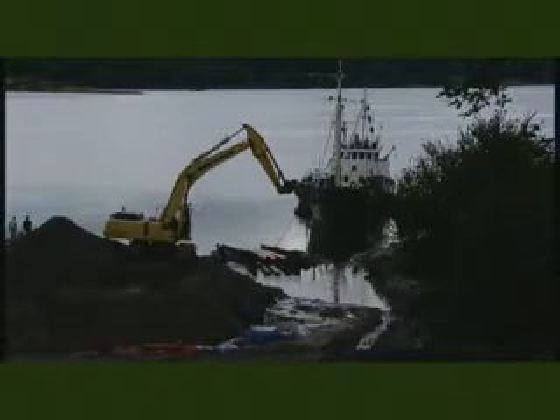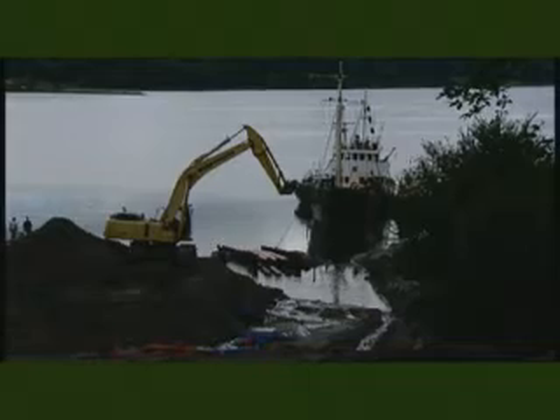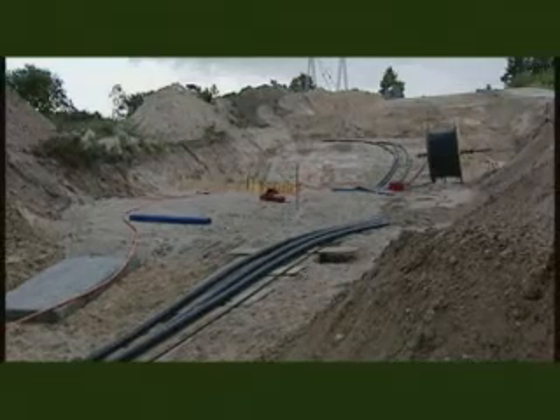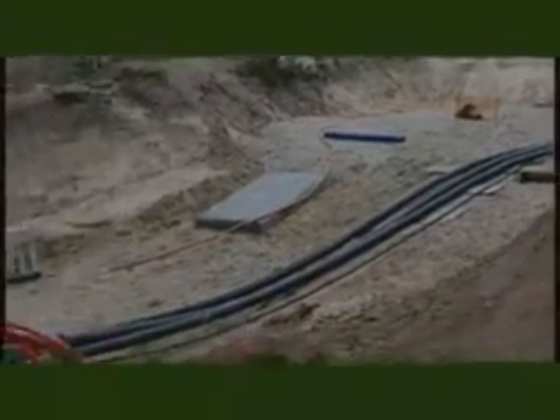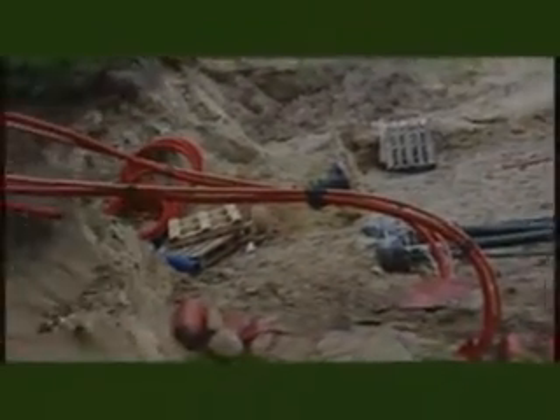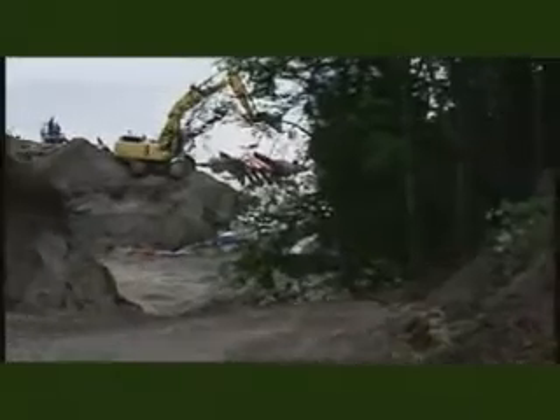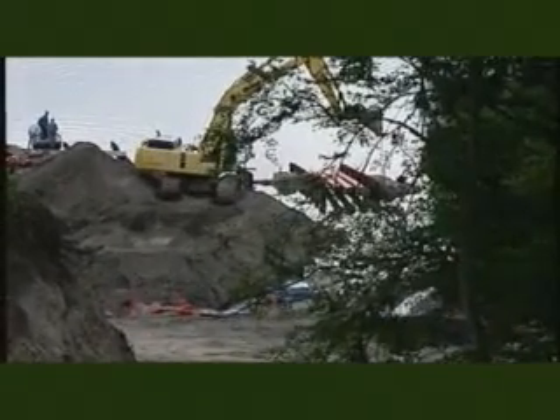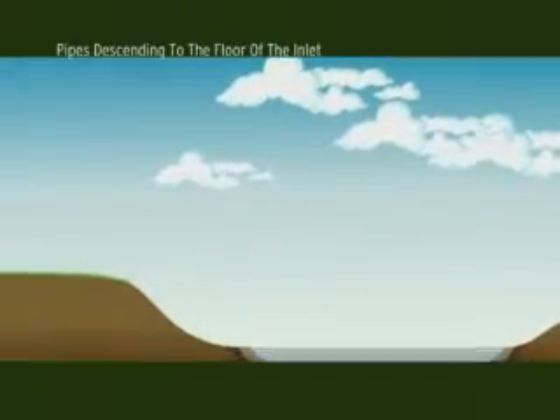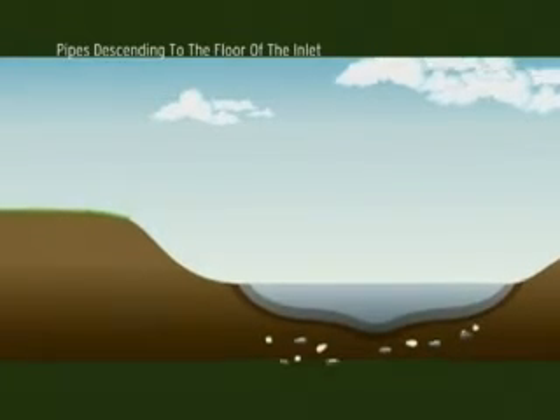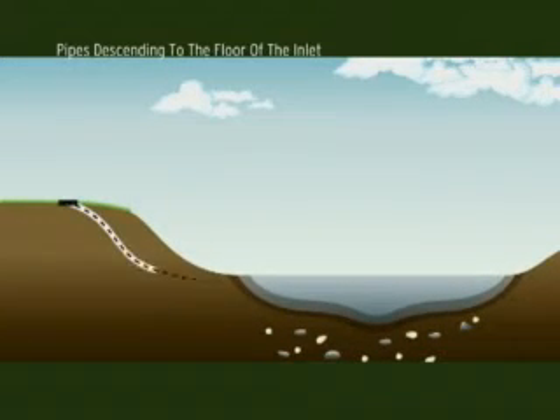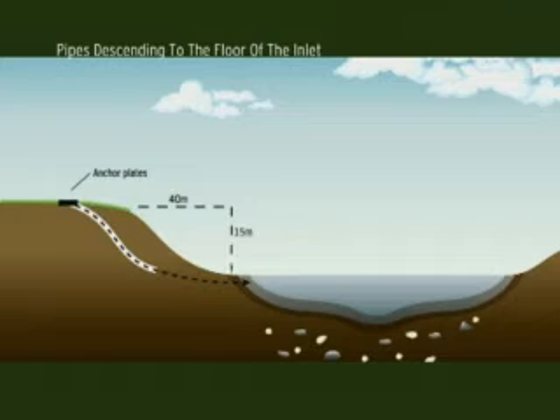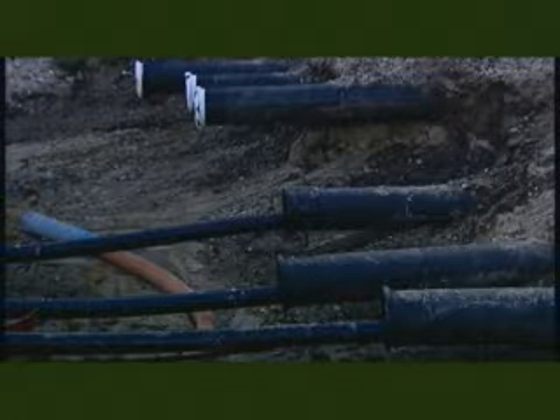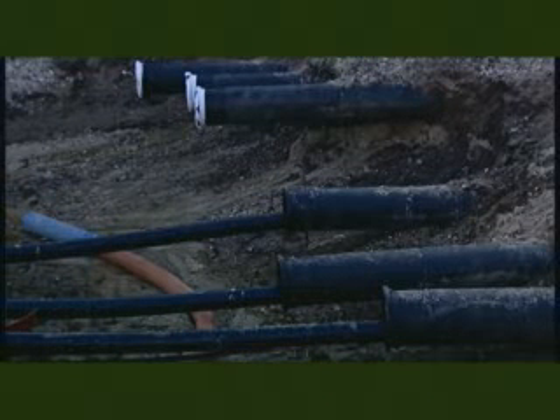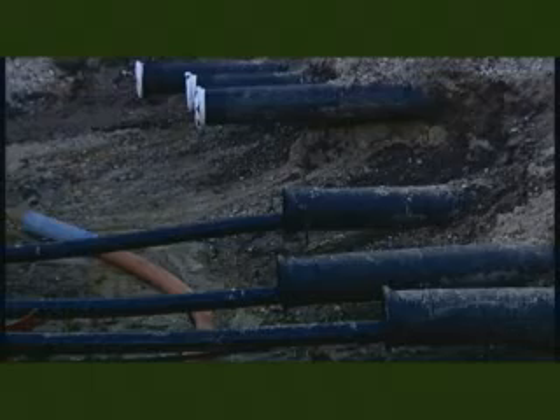To ensure that the cable does not slide down onto the beach of its own accord after laying, an anchor plate was established at the top of the slope, to which the cable could be secured. The bank down to the beach is so steep that it's not possible to lay the cables in open trenches on site. It was therefore necessary to carry out a controlled directional drilling beneath the slope. The cables are fed through the pipes down to the beach. After laying, the pipes are sealed with customised end plates, after which they're filled with bentonite.